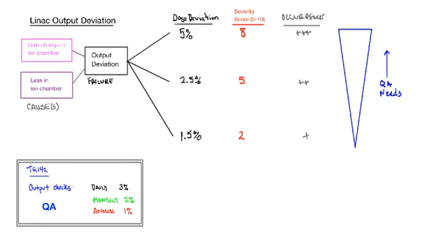So one thing you might be wondering as you look at the information from this example is about frequencies and sensitivities. You'll see we have a test here that's sensitive to output variations at the 1% level. So you might ask, why don't you just use that every day and be done with it? It's a good question, and it has to do with how easy it is to perform those tests. We'll see this in the coming videos.